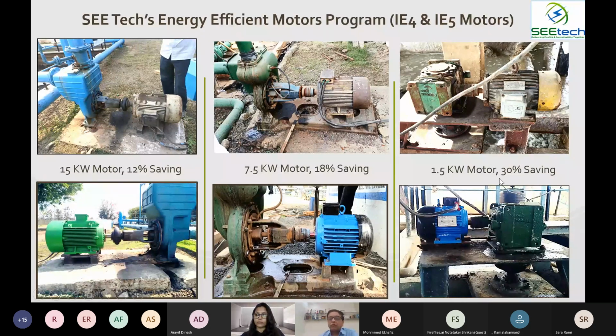So what happens is, particularly on a smaller motor, you get a higher percentage saving, but the cost of the motor on a smaller size is much higher. Whereas on the higher kilowatt size motor, the percentage saving is less, but the cost per kilowatt of the IE4 or IE5 motor reduces. So practically you get a similar payback period, despite such different percent savings. Your payback periods are usually around 2 years for these kinds of projects.